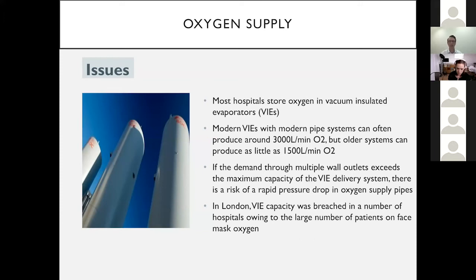In the UK, most hospitals have oxygen supplied via vacuum insulated evaporators, which have a limited flow capacity. The risk is that if demand exceeds that supply, there's a risk of rapid pressure drop in the oxygen supply lines, putting patients at risk.